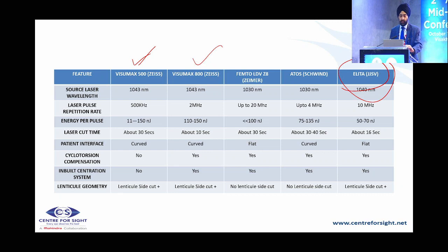India is taking a global leap forward in bringing lenticule extraction platforms to the table. The laser source for all machines is approximately the same at 1043 nm. When looking at pulse repetition rate, newer lasers have higher rates — meaning they move faster. The 500 was 500 kHz, the 800 went up to 2 MHz, and the Ziemer can go up to 20 MHz. Overall, procedure time has gone down significantly, from 30 seconds to 10-16 seconds, with VisuMax 800 and ELITA being the fastest.